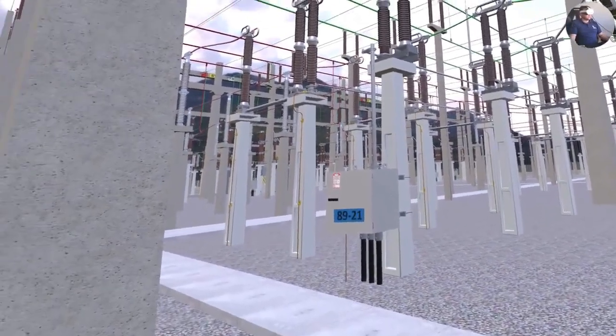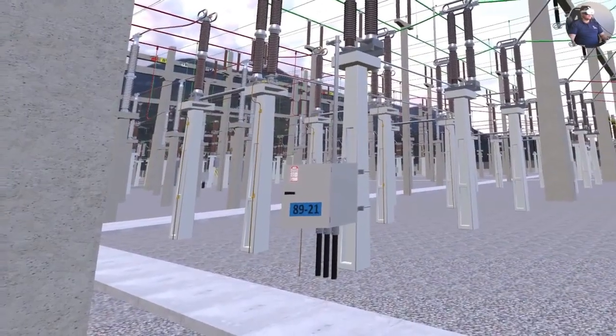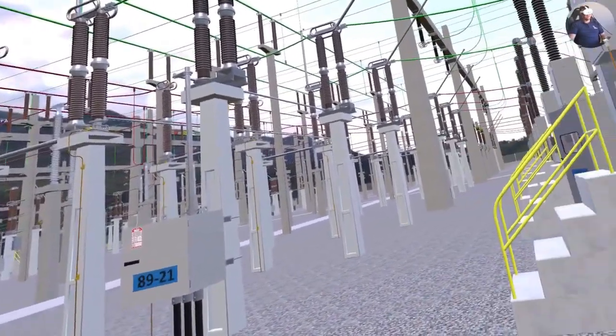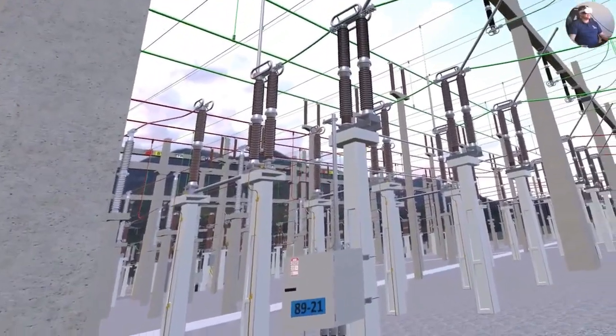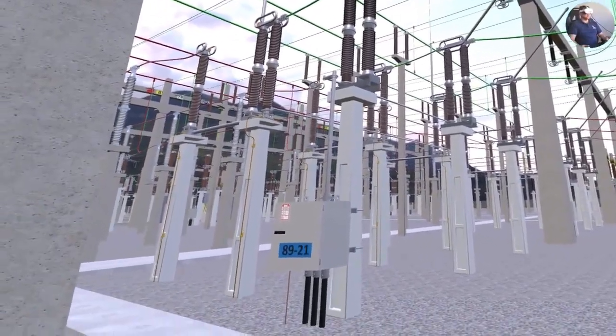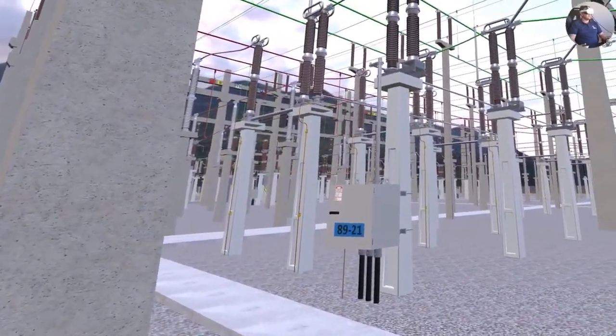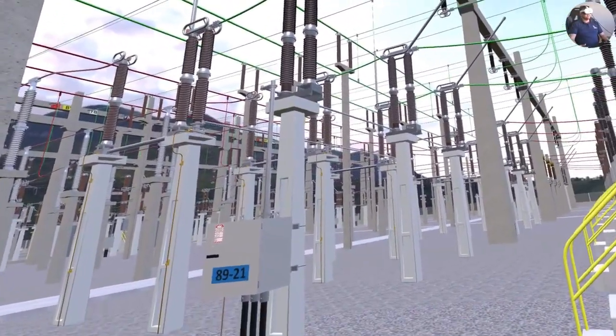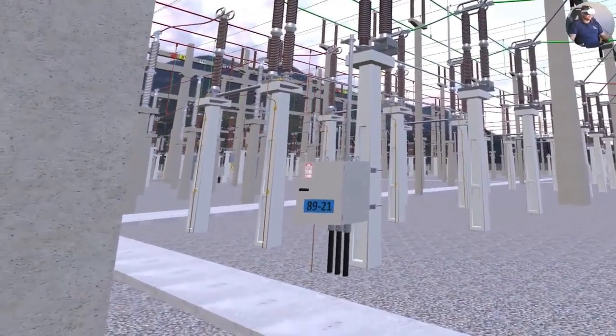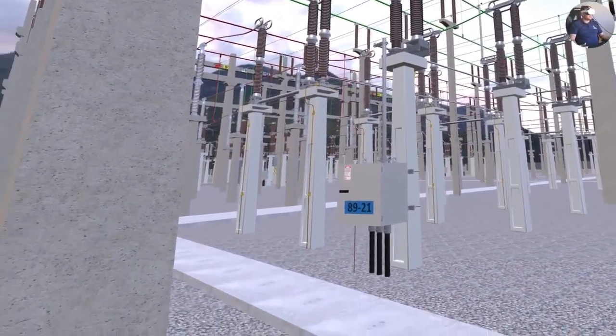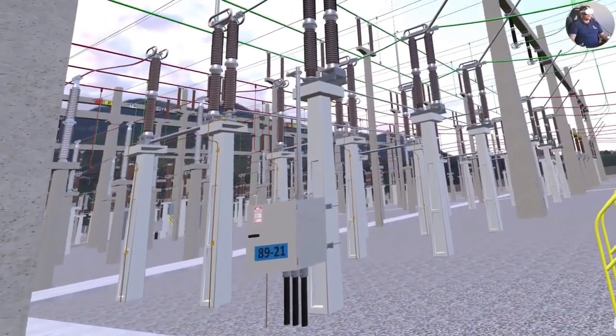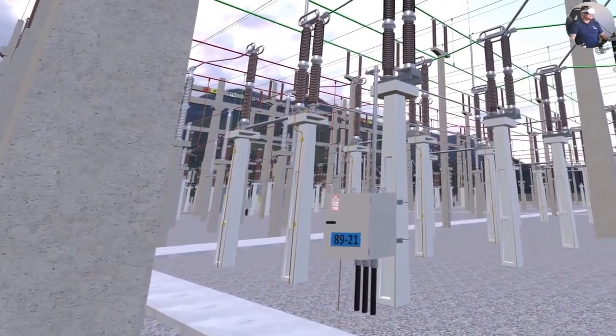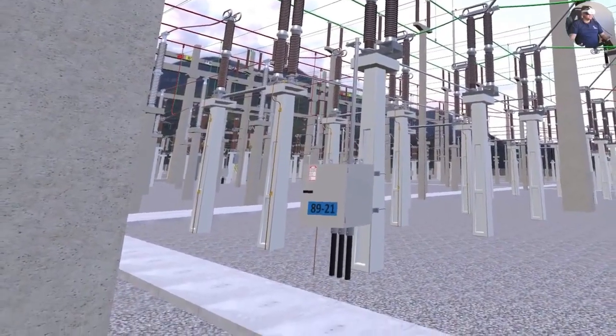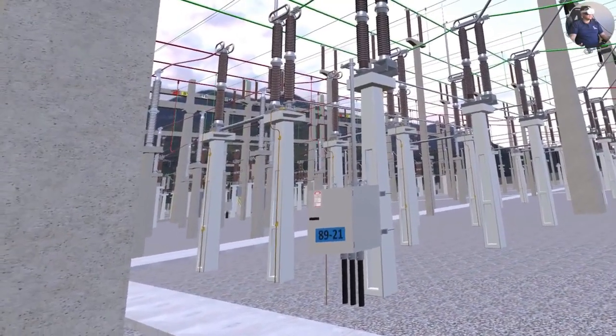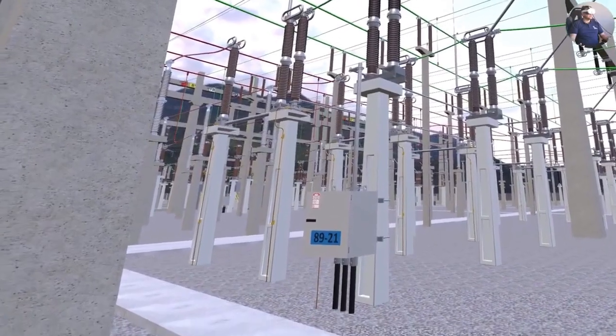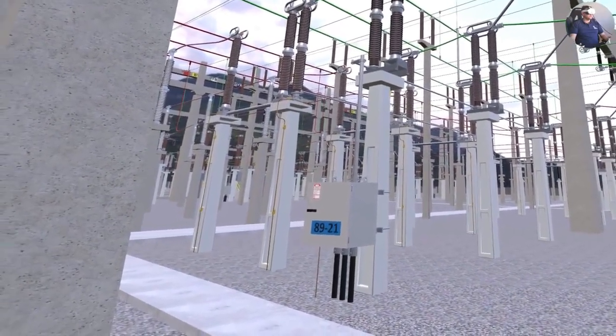Guys, we finished de-energizing the transmission function here, the AT2 transformation, and now in this lesson, we're going to perform the energization. We're going to bring this function back into operation here, okay? So we're going to perform the reverse maneuvers here, right? Before we started by opening the circuit breakers and then opening the disconnect switches. Now we're going to start by closing the disconnect switches, and then finally we'll close the circuit breakers both in the 230 sector as well as the 138 kV sector, and also the breaker there in the 13.8 kV cubicle.